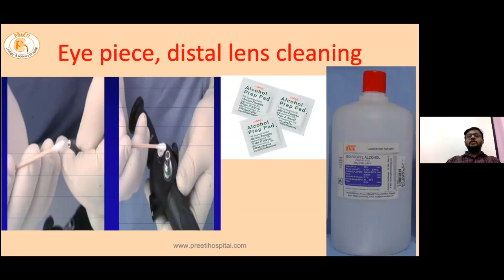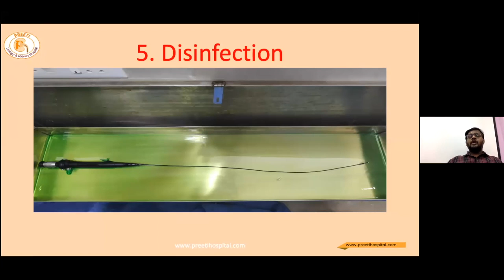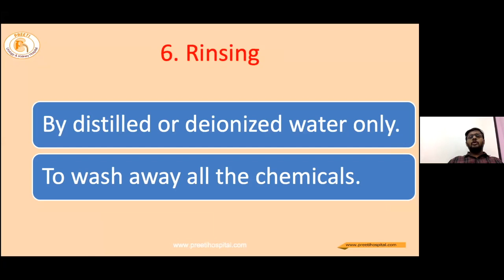And disinfection is the main heart of the high-level disinfection program. Whatever disinfectant you use, the most important thing is to make sure that your scope is fully immersed in the disinfectant for the adequate prescribed contact time. Once the scope has been immersed in the disinfectant for the adequate time, the scope is rinsed of all the chemicals, where commonly only deionized water or distilled water should be used.